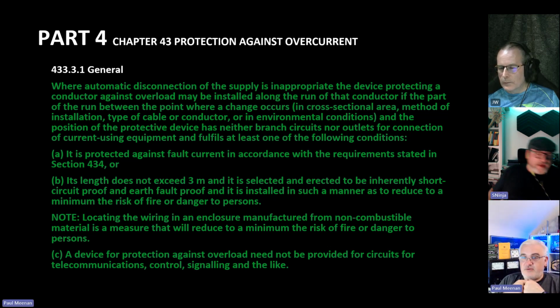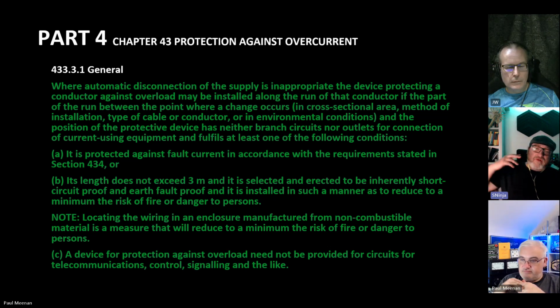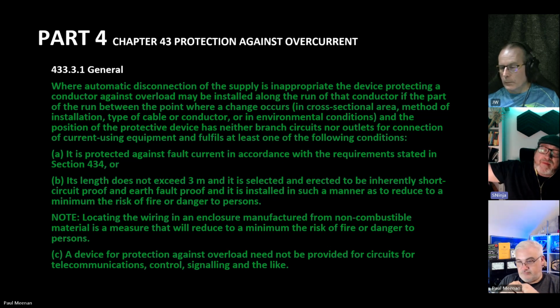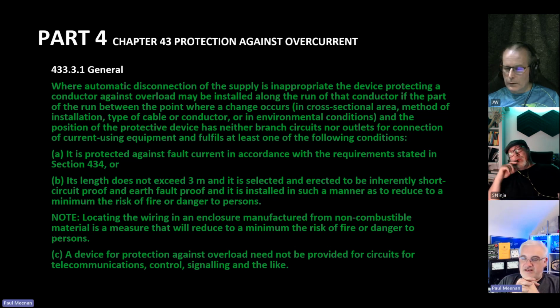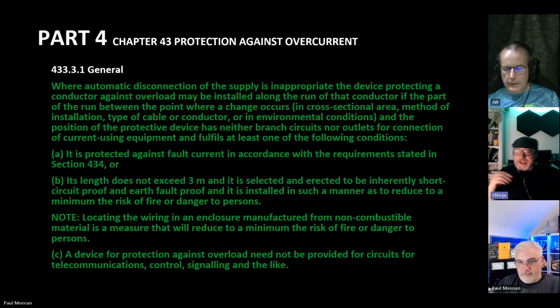Yeah. Another common example of that is a car park light circuit, where you may have a long run to the outside car park. You'll have like a 6 mil, but you may have a 6 amp breaker in the board. Yeah. So when you change a 6 mil down to a 1.5 or a 2.5, you don't have to change the overcurrent device because you've got it at the beginning. Yes, yeah. So I think that's what they were trying to say, unless they were trying to say also don't run a 1.5 mil and then transition to a 35 mil. It's just about the way it's running.